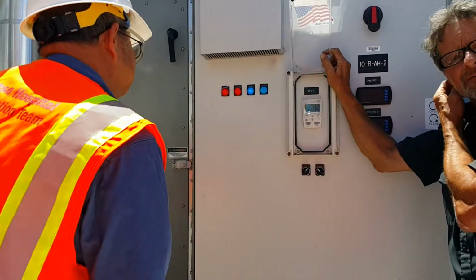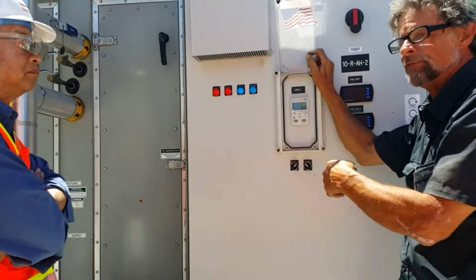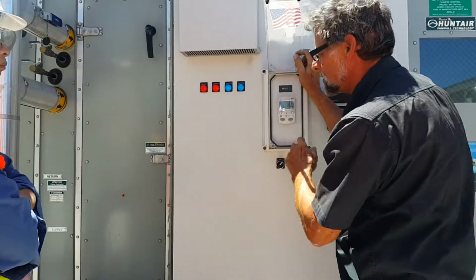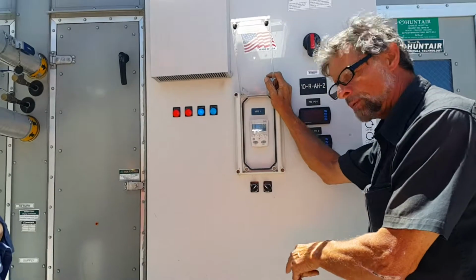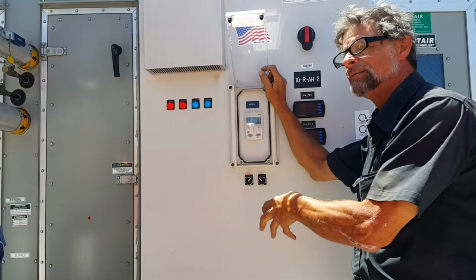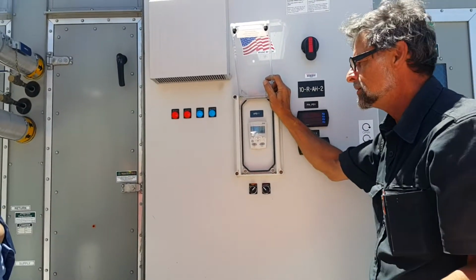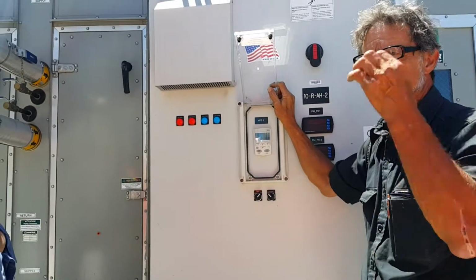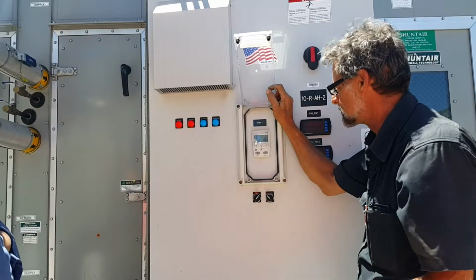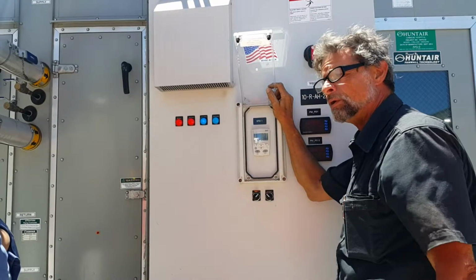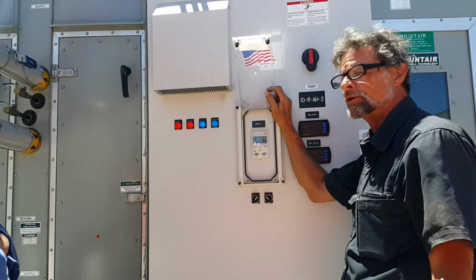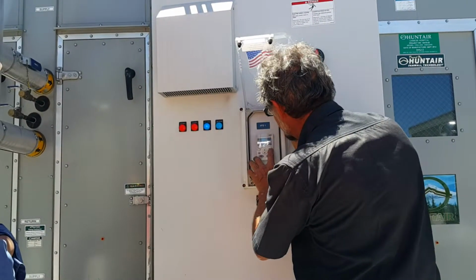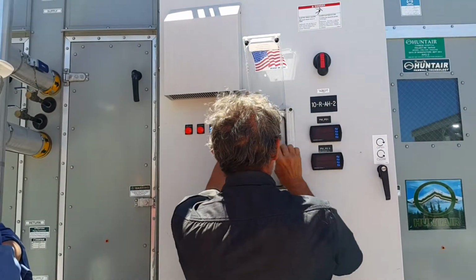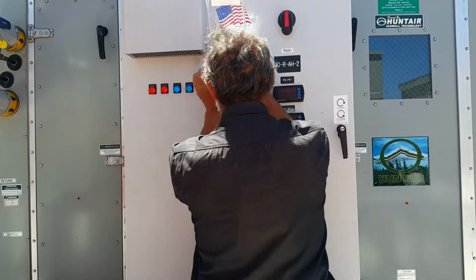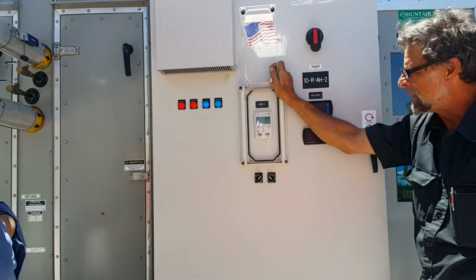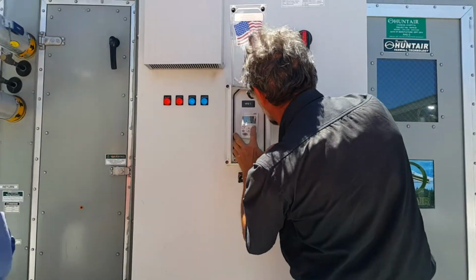So once this gets turned over to you, I would advise doing a parameter backup, because even at startup, if I make some changes to what I wanted to do or I think it should do, controls people might come in later, they might change the input signal or do some things. So when you get a hold of it and everybody else is out of here and there aren't going to be any more changes, you go to parameter backup, and the top line is upload to panel. It may not work unless the thing's turned off.